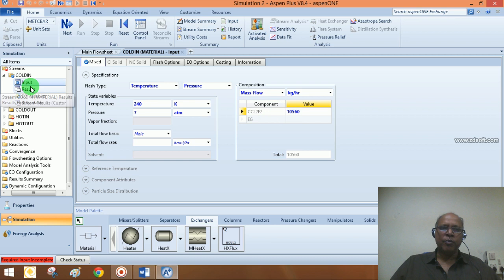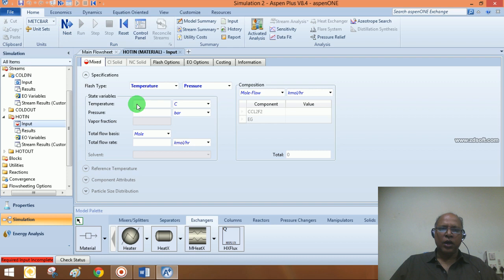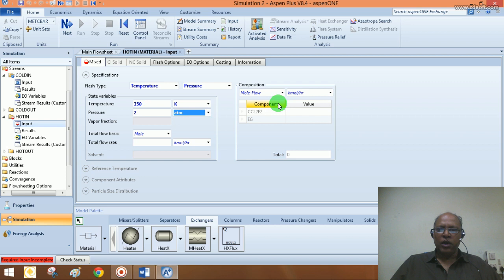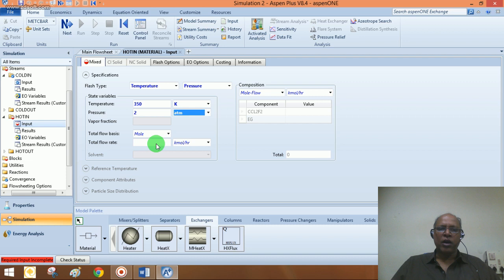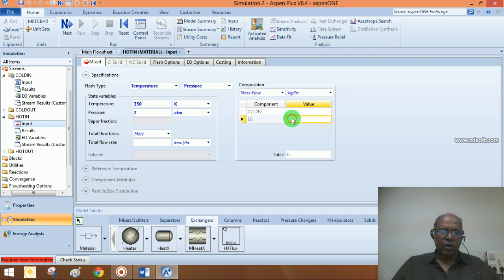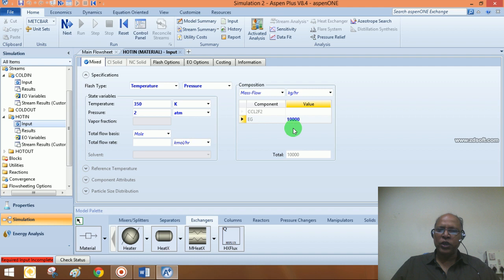The hot stream inlet is at 350 Kelvin, pressure of 2 atmospheres, and it is pure Ethylene Glycol. We need to specify the flow rate. Since we know the hot stream outlet temperature should be 320 Kelvin, but that cannot be provided as a stream input, let me make an assumption — a wild guess of about 10,000 kg/hr, since the cold stream enters at 10,560 kg/hr. We will review this after running the simulation in rating mode.